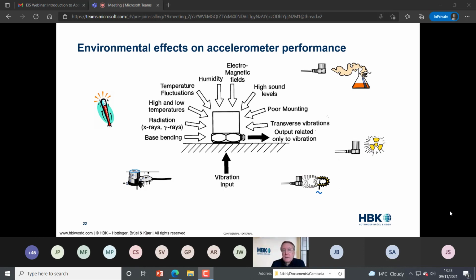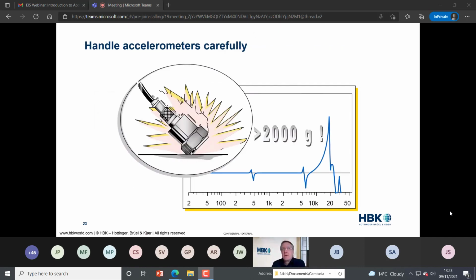Accelerometers are sensitive to acoustic signals. So if you are measuring a low vibration level in a very high sound level, it may be that your vibration output is being contaminated. And that goes for all of these influences. Something that is very important with piezoelectric accelerometers is they do not like to be dropped.